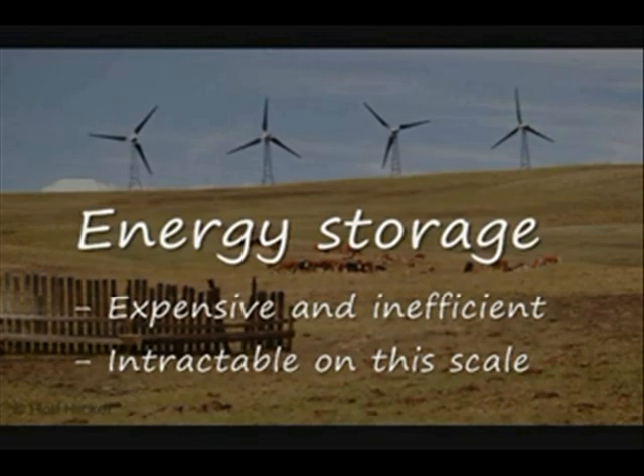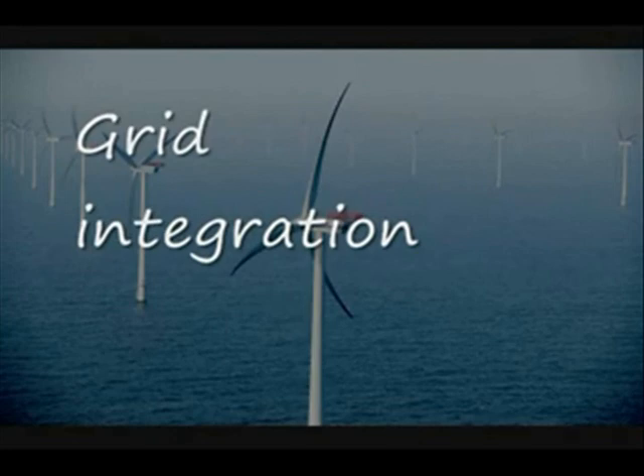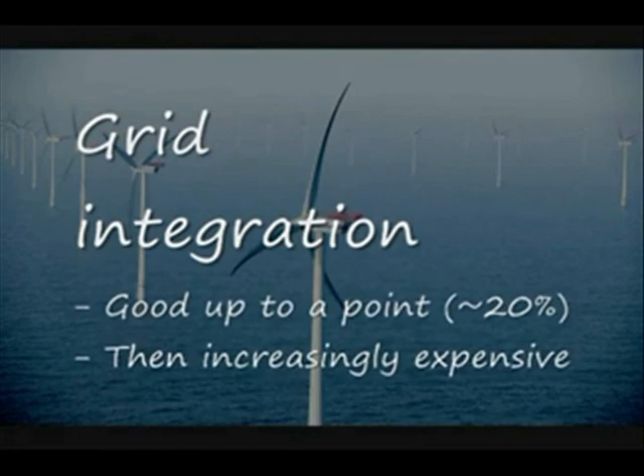I'll explain the advantages and drawbacks of different types of energy storage in a later video, but it's enough to say that large-scale energy storage is too expensive and too inefficient to be an option for now. Wind power doesn't require energy storage by its nature — it's all a matter of scale. Up to some level of penetration, generally thought to be around 20%, there is very little cost to integrating wind with the existing grid. That is, even without any form of energy storage, up to 20% of our electricity can be provided by wind without sacrificing reliability or cost-effectiveness. The simple explanation is that for every kilowatt-hour produced by a wind turbine, there is one less kilowatt-hour of demand being placed on other generating plants like nuclear, coal, or natural gas. This doesn't help us, though, at very high levels of penetration. Beyond that magic threshold of around 20%, it starts to get more and more expensive to integrate wind into the grid without energy storage.